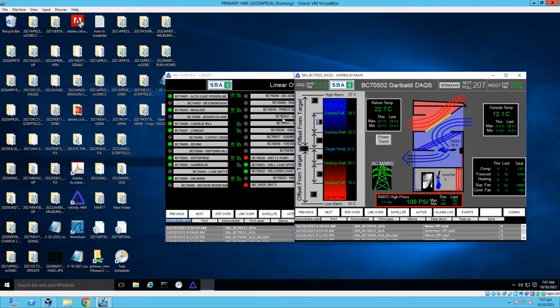On the left, we have our active set points, which start with a target temperature and have a differential setup for controlling heating and cooling cycles. In this case, 1 degree above target, cooling starts and scales to its maximum cooling capacity 3 degrees above target, followed by a high alarm 6 degrees above target. Respectively, the heating set points are set up in a similar fashion.